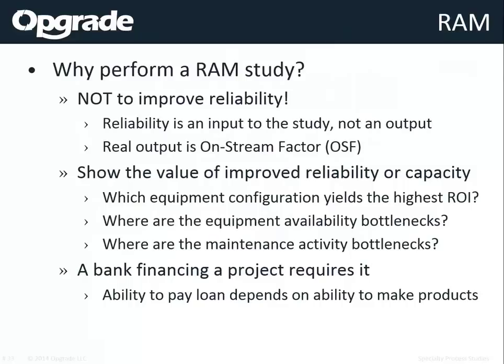That single number is based on a million different assumptions. The real value isn't in that one number — it's in changing one assumption, such as the capacity of one piece of equipment, and seeing the output go from 95.23% to 95.33%. That change gives you high-confidence knowledge of the value of that specific improvement.